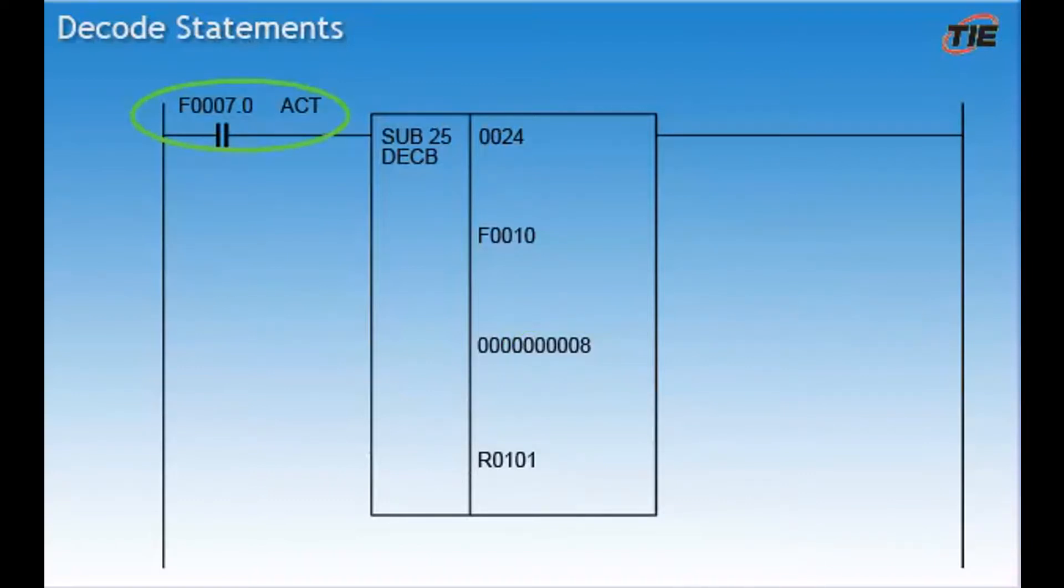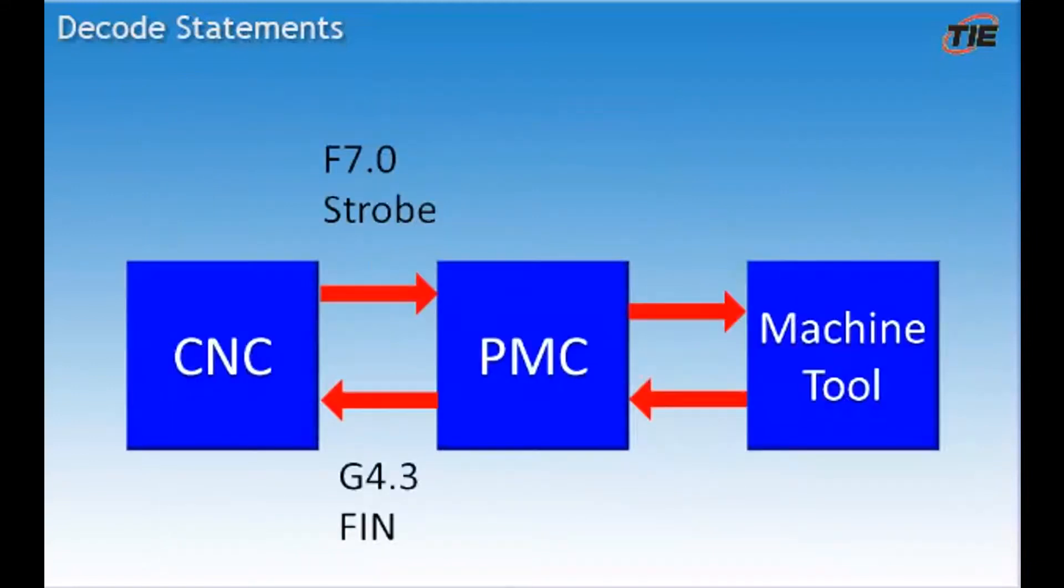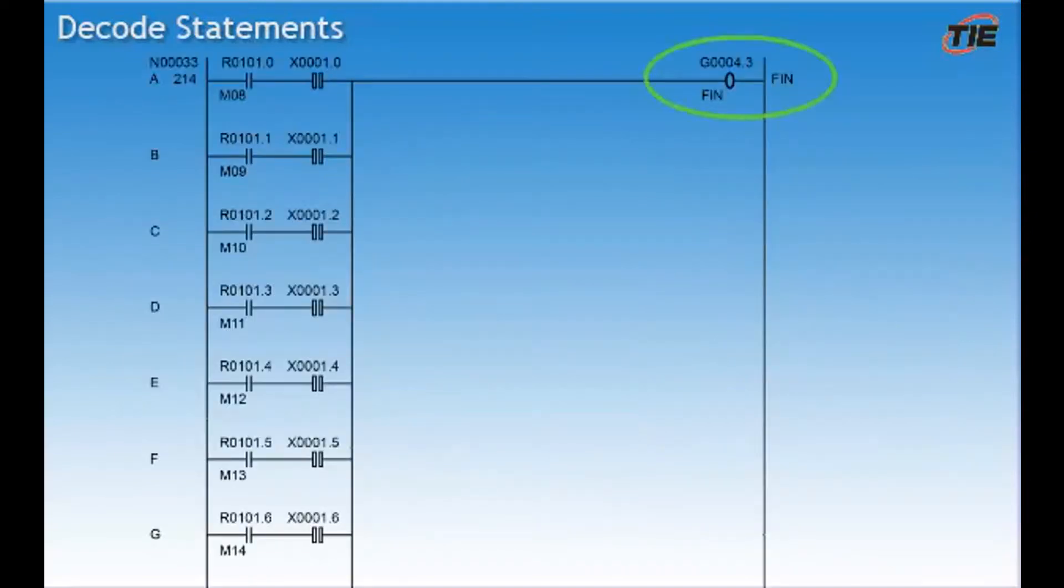Once the output is turned on, it stays on. This is due to the strobe signal, F7.0, still being active. The strobe signal will remain active until the FIN signal is received by the CNC or the control is reset. The FIN signal, G4.3 or G5.0, is activated in the ladder logic by the machine tool builder. This happens once the M code operation has completed. For instance, the door is finished closing, the ATC operation has completed, or the indexer has completed its move.